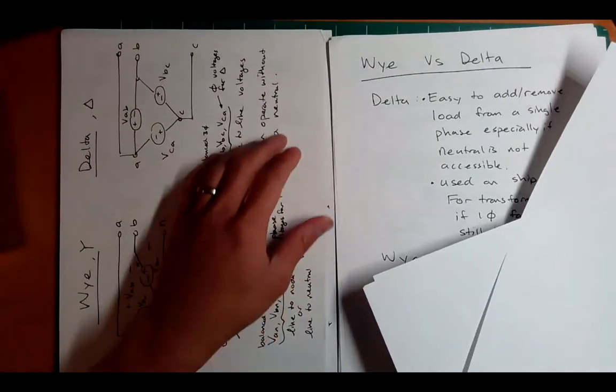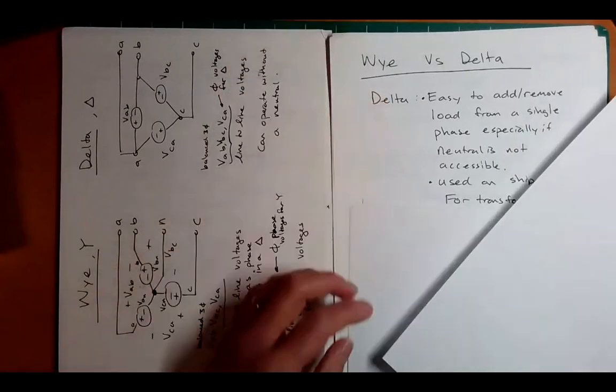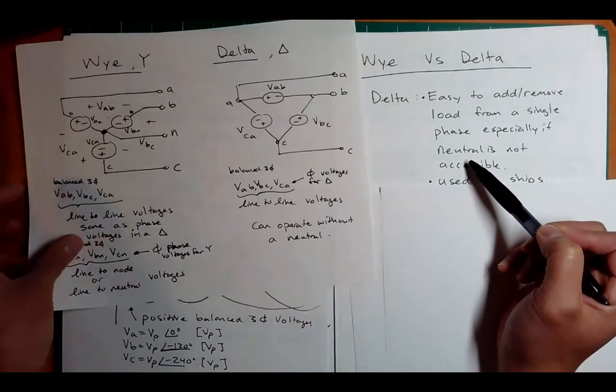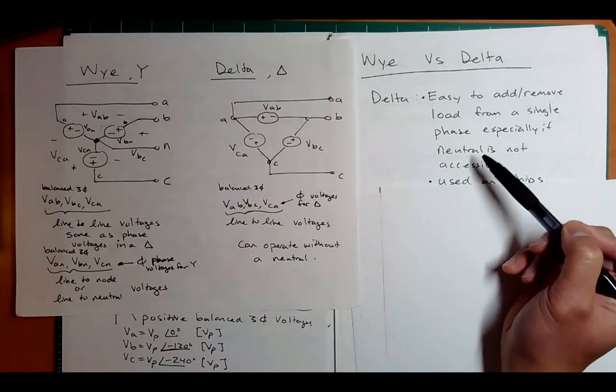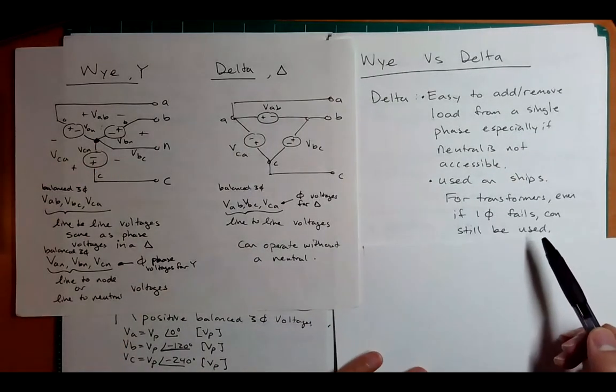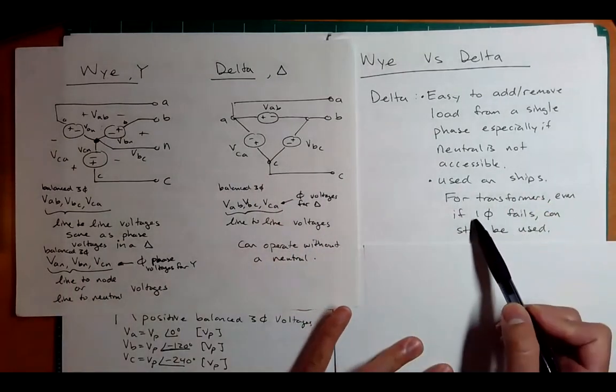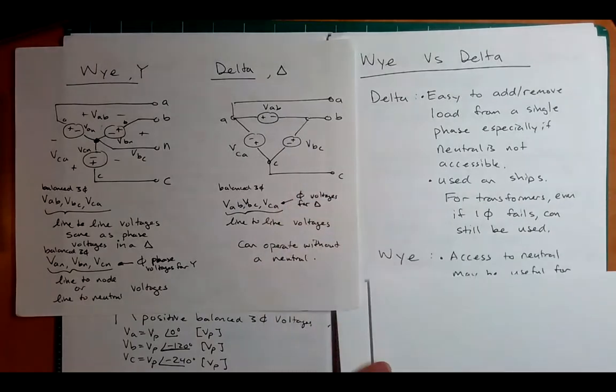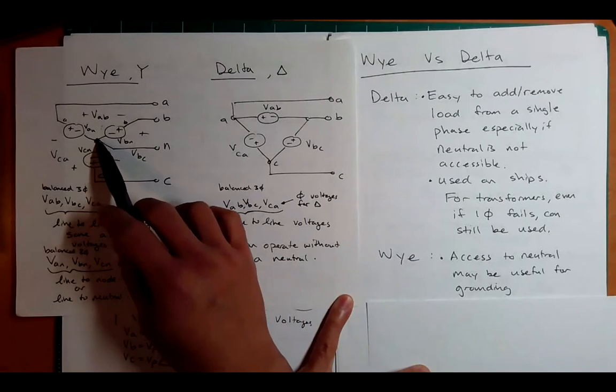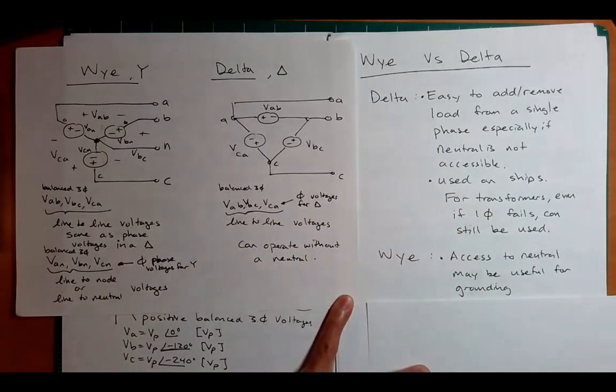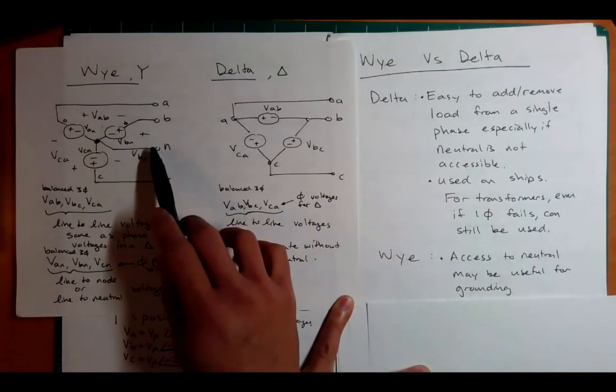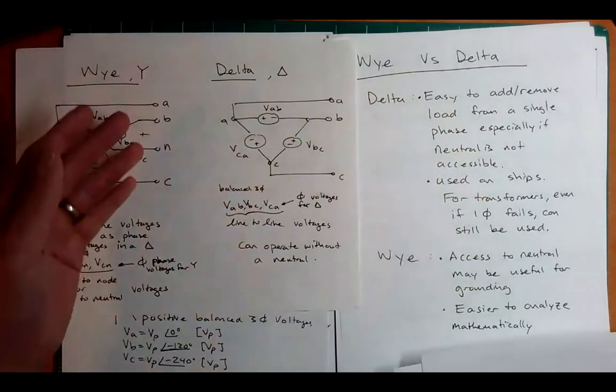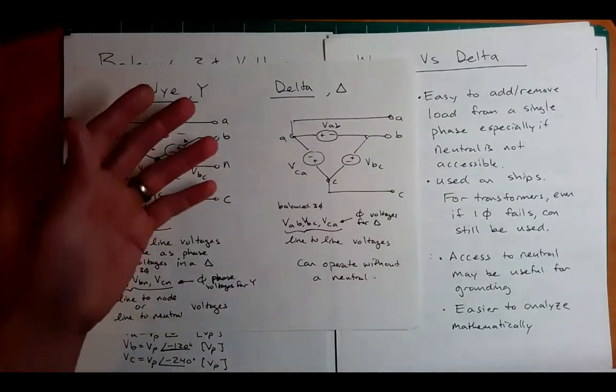Comparing Y versus delta: for delta, it's easy to add and remove load from a single phase, especially if the neutral is not accessible. On three-phase transformers, the nice thing about a delta-to-delta transformer is that if one phase fails, you still get three-phase voltage and current — some redundancy. A Y configuration might be nice because you can access the neutral for grounding, and the Y is also easier to analyze mathematically.